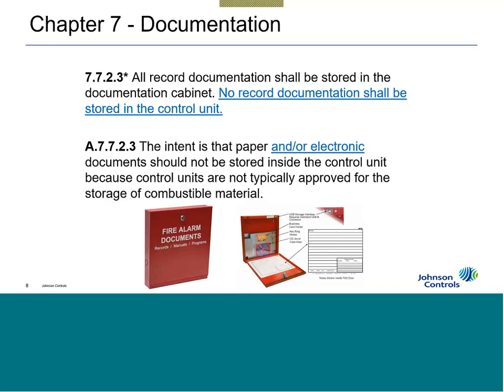So much so that NFPA's liaison came to the committee and said, look, I keep getting questions and I see problems with this, and people still putting documentation in the control units. Can you help us with that? So typically codes and standards are written in positive language, not negative language. Usually they tell you what you have to do or should do, but not what you don't have to do or what you shouldn't be doing. So here's a case that's kind of unique when you see the "no record documentation shall be stored in the control unit."